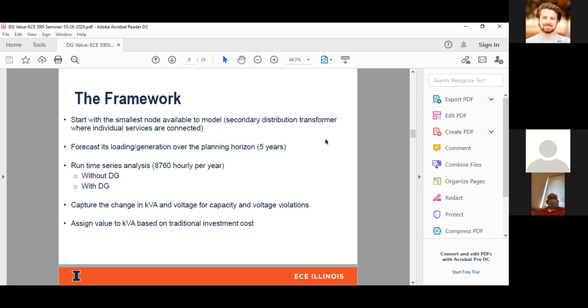And you forecast that for 5 years. You run the analysis without DG, and then you run the analysis with DG with incremental increase of that specific DG type that you're trying to preemptively calculate until you get, like we said, the diminishing returns stopping point. And then you start calculating what that monetary value is based on a comparison to the typical upgrade. We'll go through an example of that.